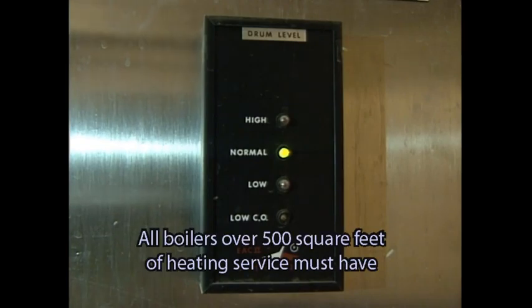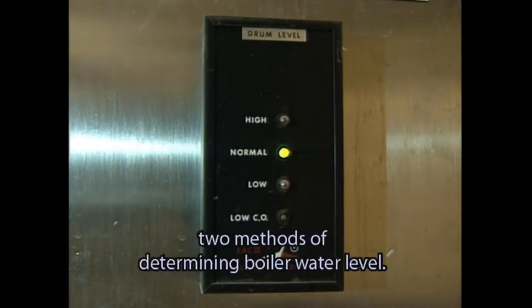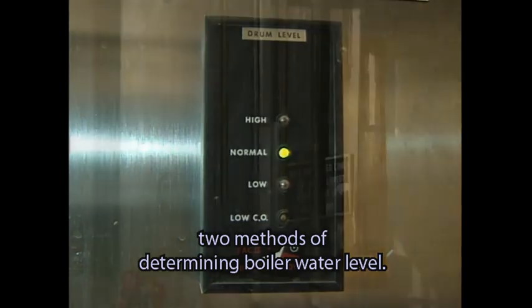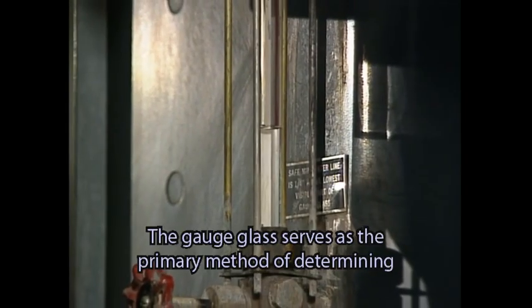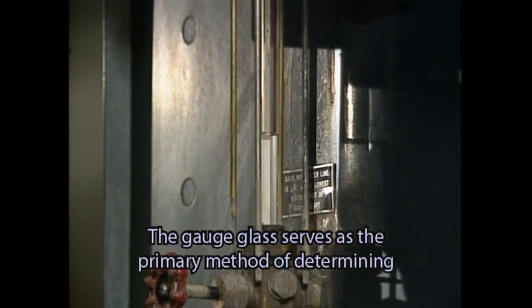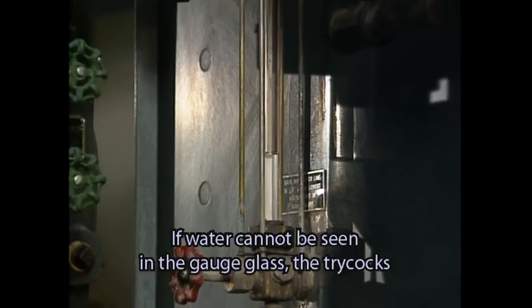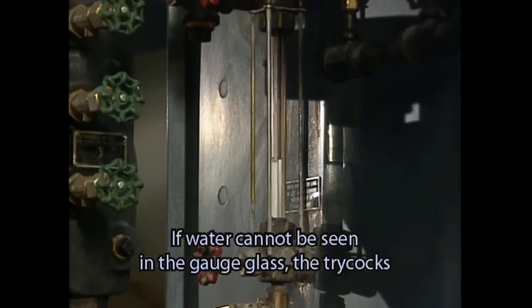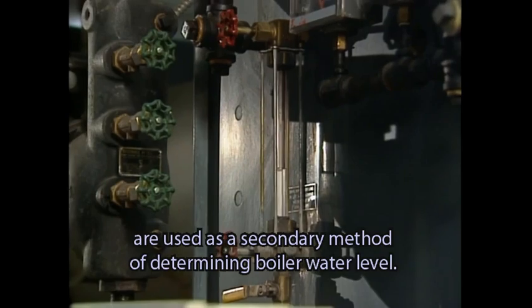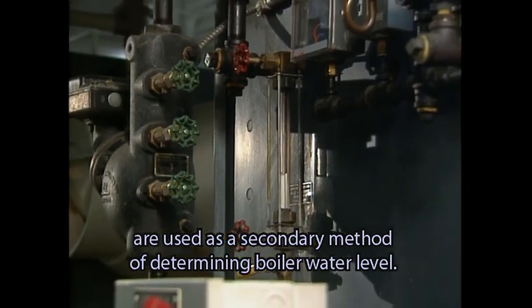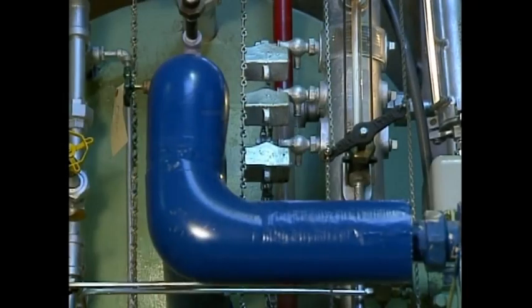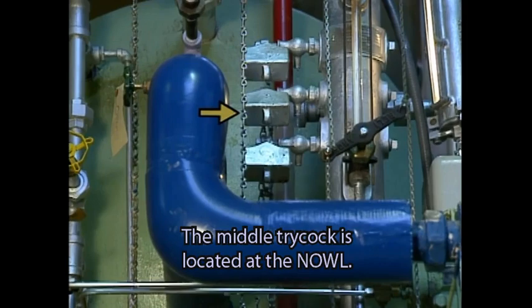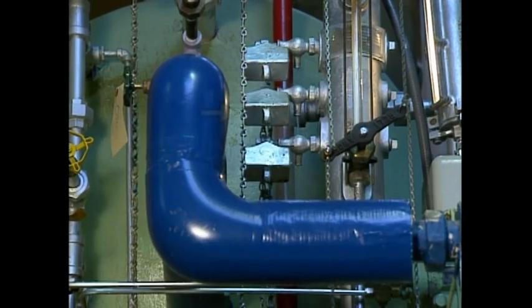All boilers over 500 square feet of heating surface must have 2 methods of determining boiler water level. The gauge glass serves as the primary method of determining boiler water level. If water cannot be seen in the gauge glass, the tricocks are used as a secondary method of determining boiler water level. The middle tricock is located at the NOWL.